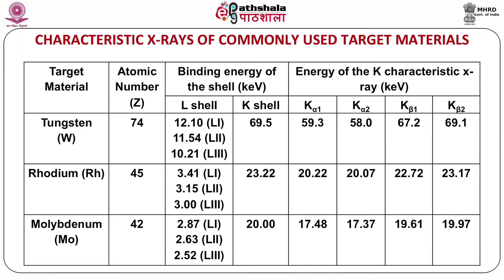So the energies of the K characteristic X-rays of these targets are, for example, K alpha 1 X-ray has energy of 59.3 keV, K alpha 2 58 keV, K beta 1 67 keV, and K beta 2 69 keV for tungsten. In case of rhodium, K alpha 1 has energy of 20.2, K alpha 2 20.07, K beta 1 22.72, K beta 2 23.17, and for molybdenum, these energies respectively are 17.48, 17.37, 19.61 and 19.97.